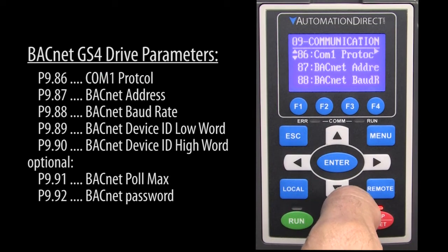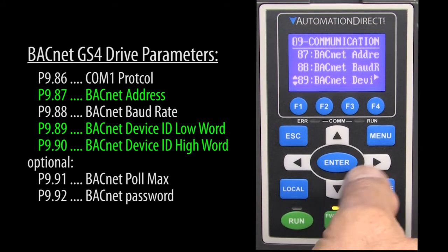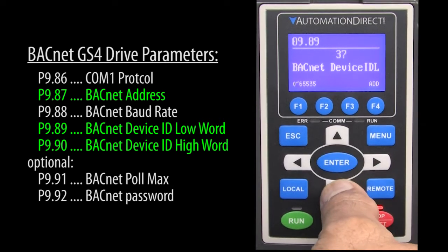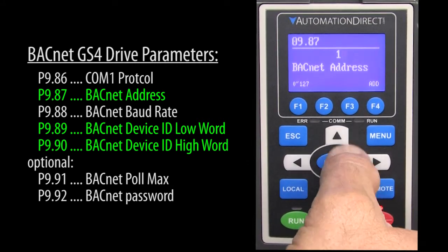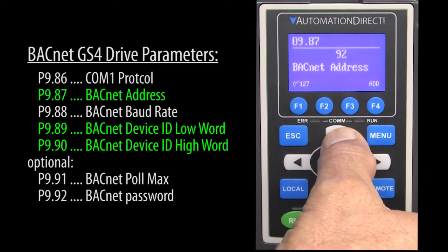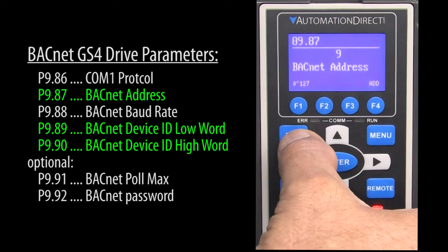You'll want to make sure that the BACnet address and device IDs are unique on your BACnet network. Let's change our ID from the default 10 to 37 and the address to 99, just so it's obvious that we found this device.